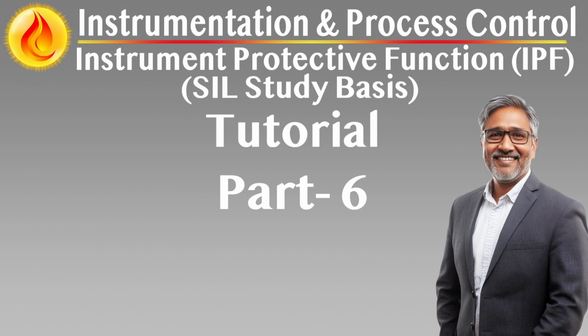This functionality is designed to support scheduled testing, calibration, or maintenance tasks while minimizing the risk of accidental trips, unsafe bypasses, or loss of protection. Unlike manual overrides, which are initiated case by case, an automatic MOS is predefined, pre-validated, and embedded into the system logic. It ensures consistency, traceability, and safer execution of routine interventions on critical IPFs.